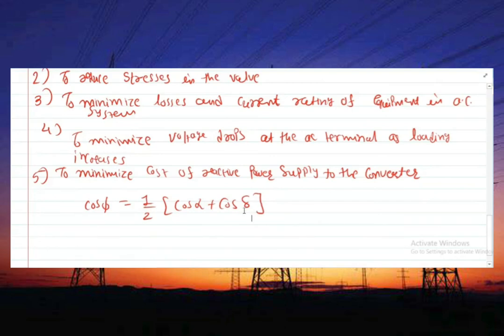The rectifier however has a minimum limit of alpha about 5 degrees to ensure sufficient voltage across the valve before firing. In inverter it is necessary to maintain a certain minimum extinction angle to avoid commutation failure. Typically the value of gamma with a safe margin is 15 degrees for 50 Hz system and 18 degrees for 60 Hz system. These are the main reasons for maintaining the power factor.